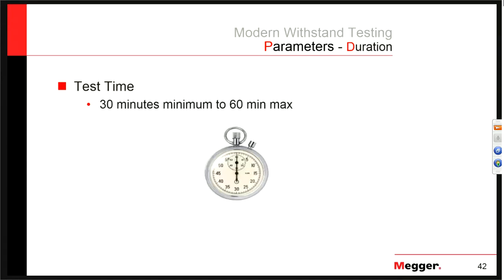Q&A: Is VLF still considered a destructive test compared to DC HIPOT? It is an over-voltage test. VLF does not put problems on your cable based on NEETRAC research, but if there are problems on the cable, it will cause your cable to fail — and that's the goal of VLF testing. In that sense it is destructive, but only if there's already a problem on the cable. It's not going to cause additional problems.